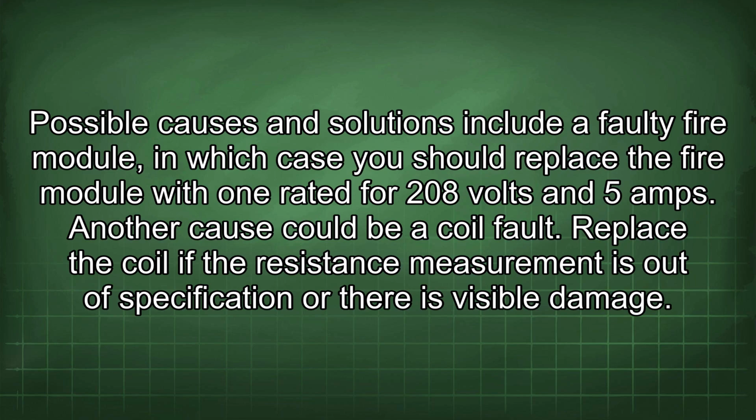Possible causes and solutions include a faulty fire module, in which case you should replace the fire module with one rated for 208 volts and 5 amps. Another cause could be a coil fault. Replace the coil if the resistance measurement is out of specification or there is visible damage.